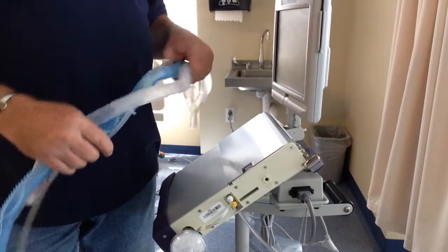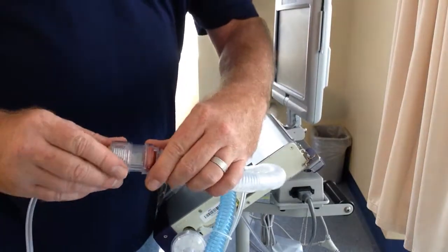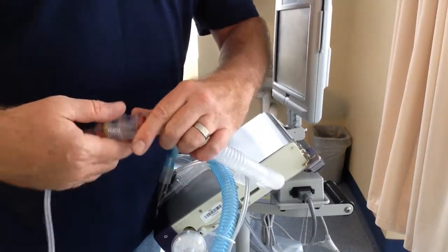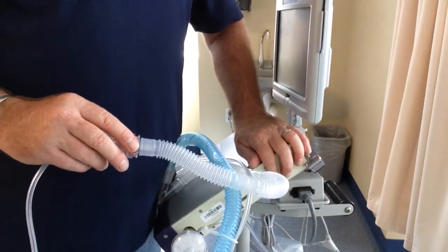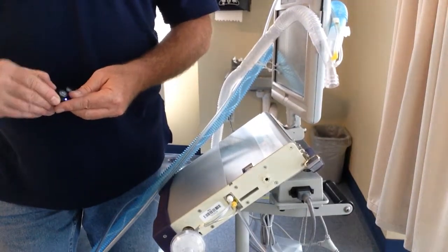Your ventilator is now up and running. One thing to point out: this circuit is actually for the LTV 1000. The 1000 does not have internal PEEP — you have to set PEEP externally. If you're using the 1000, it is a push and twist; it's an external PEEP valve just like you use on your Ambu bags. We're not going to be using this because the LTV 1200 has internal PEEP. As far as setting up a circuit, that is all the setup there is. The next video will be going over the internal controls and how to operate the ventilator.